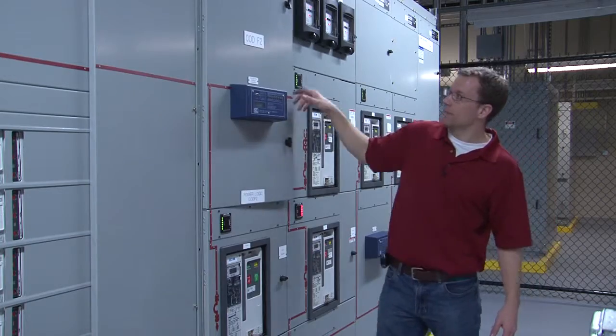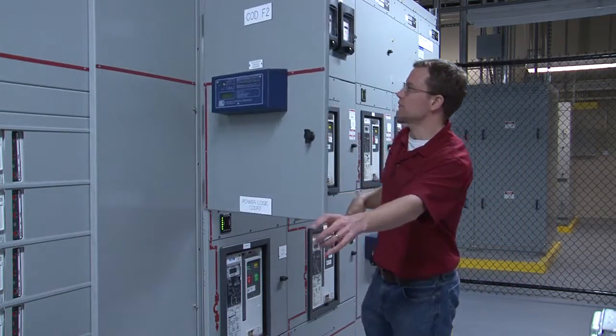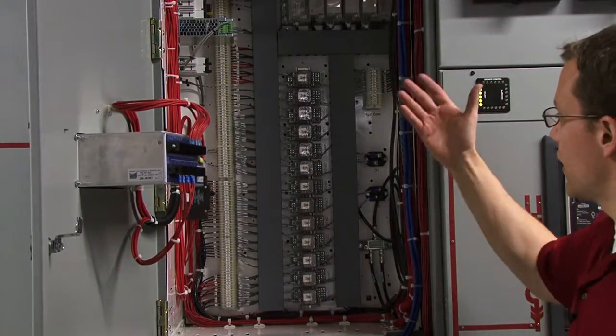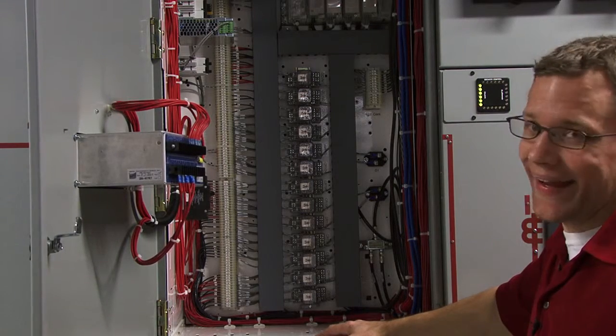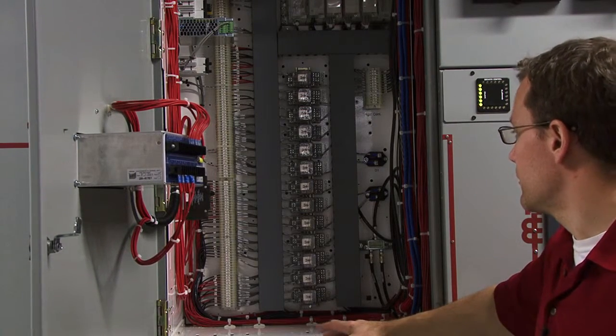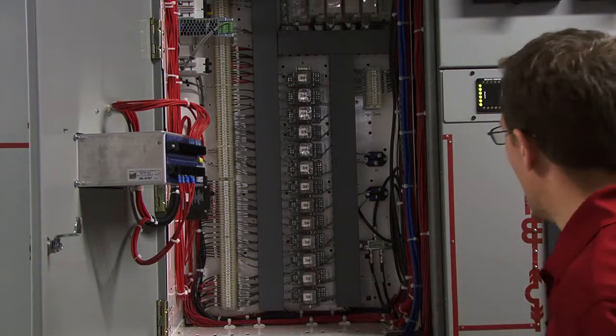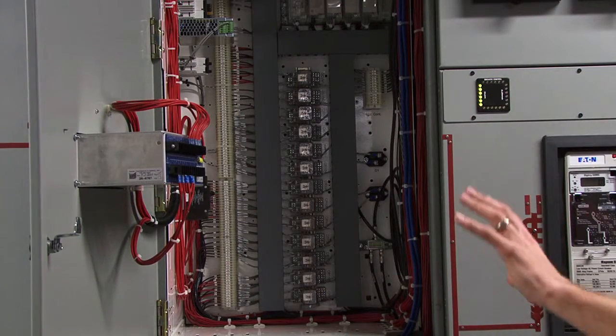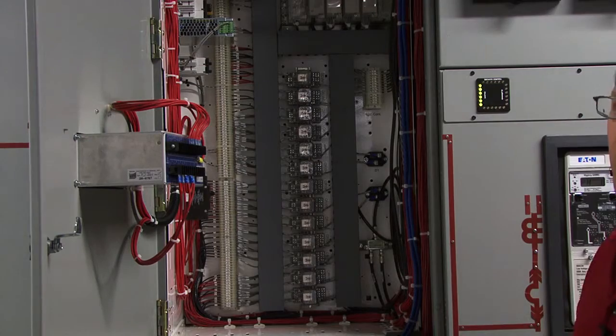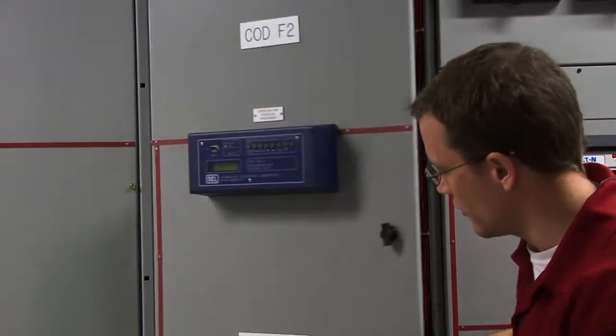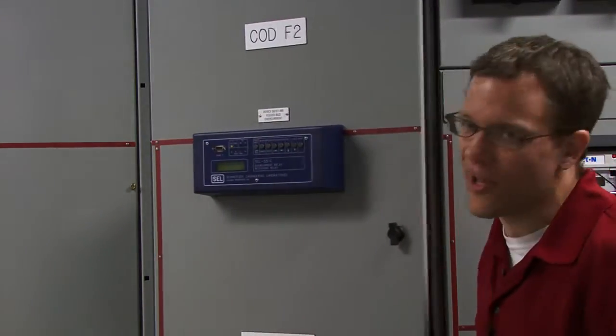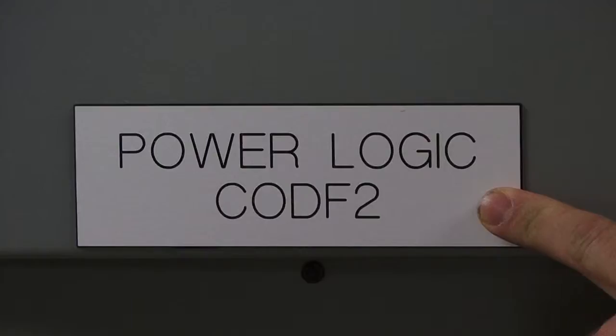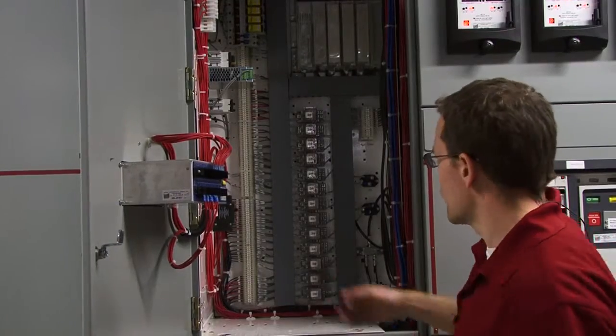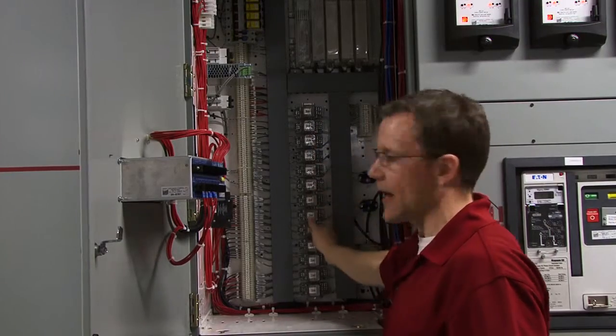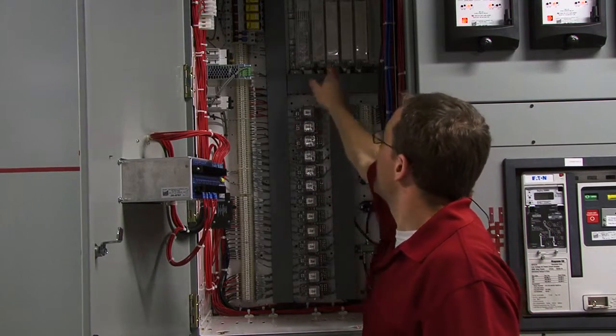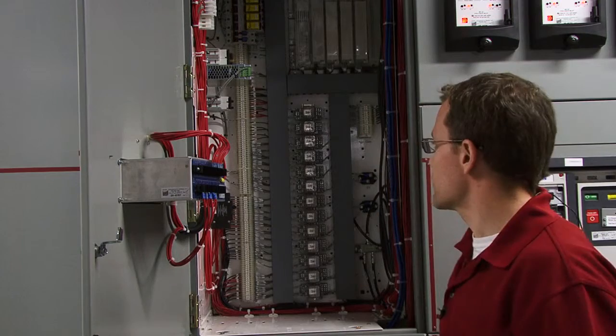In this cabinet, we have all the relaying and PLC input hardware for operating the breakers in this COD board, and they're all associated with the Square D maintenance bypass system. So it says right here, Power Logic COD F2, Power Logic meaning the Square D Power Logic system. So these relays right here are the ones that actually operate the breakers. This is the PLC inputs and outputs.